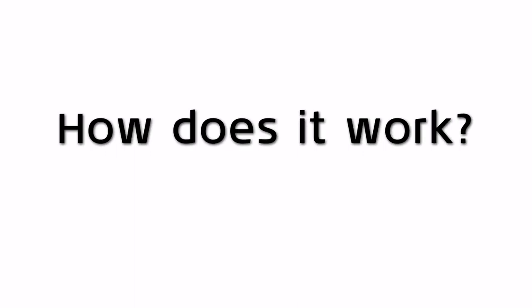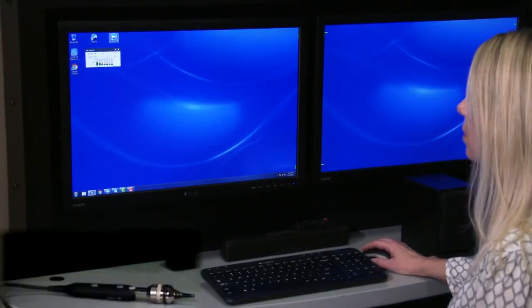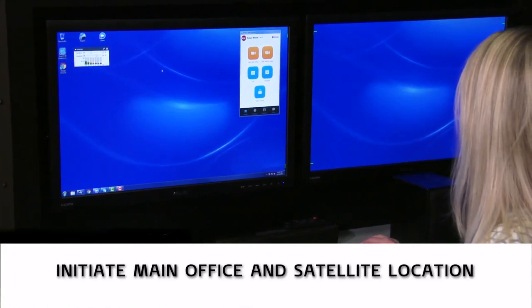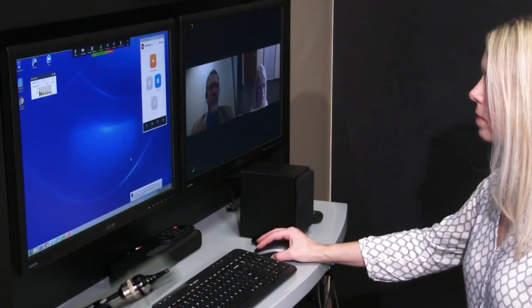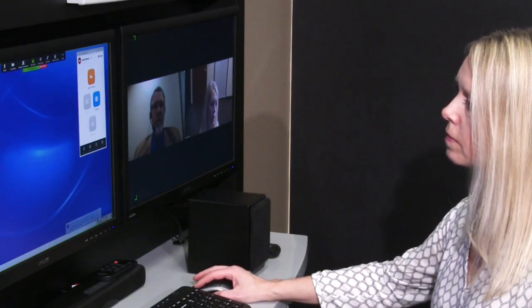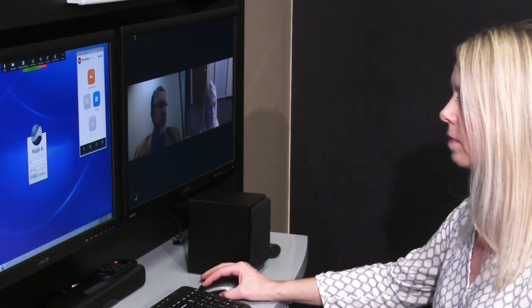The audiologist is located in the main medical center while a trained technician and the scheduled patient are located at the branch site. In preparation for the tele-aud appointment, the technician can initiate the video connection with the main medical center via information and communications technology such as Skype for Business. Depending on the protocol of the medical center, the technician may open the patient record and launch the appropriate clinic software. Finally, with a simple click, the technician hands control of the IA4500 kiosk to the main medical center audiologist.